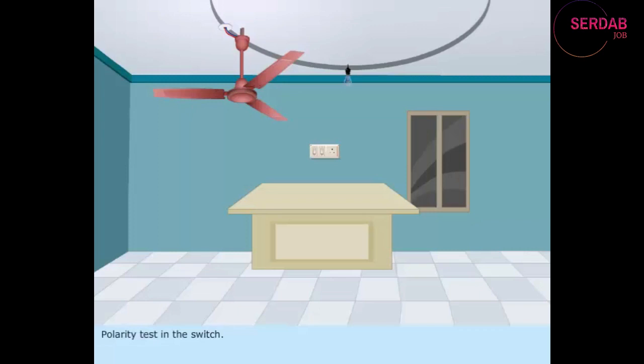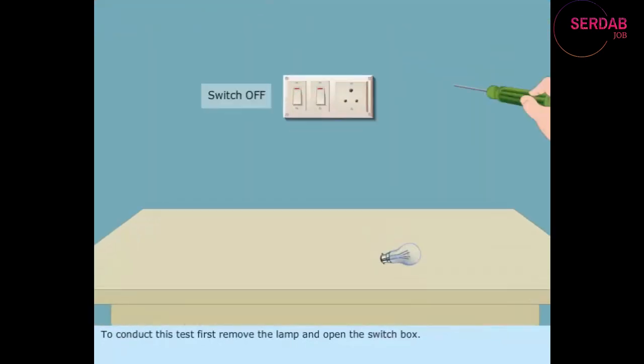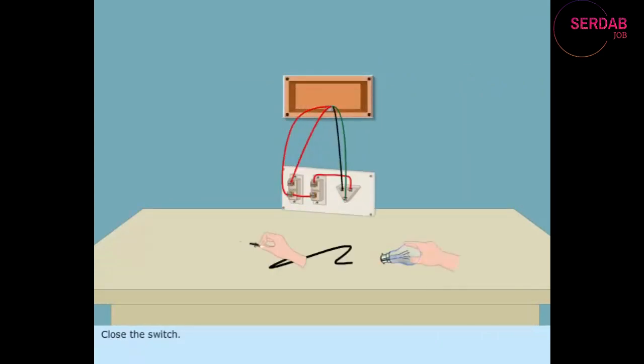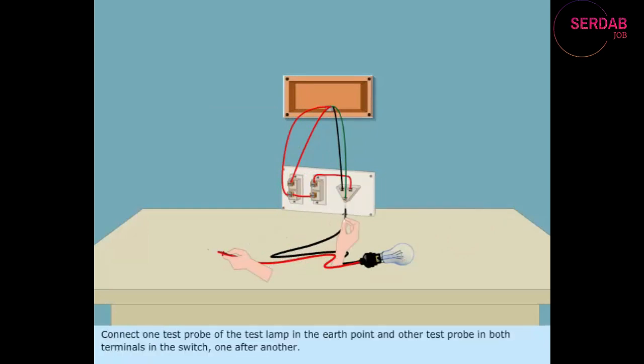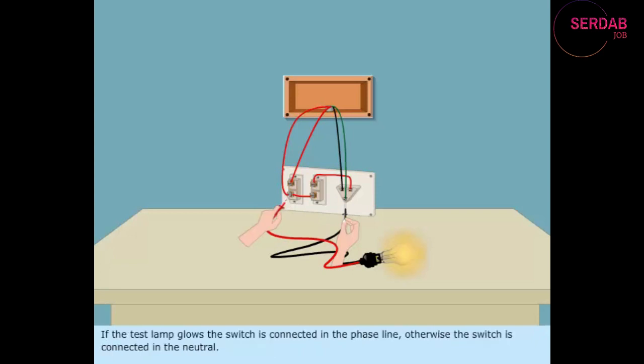Polarity test in the switch. This test is conducted to check whether the switch is connected in phase wire or not. To conduct this test, first remove the lamp and open the switch box. Close the switch. Take a test lamp. Connect one test probe of the test lamp in the earth point and other test probe in both terminals in the switch, one after another. If the test lamp glows, the switch is connected in the phase line, otherwise the switch is connected in the neutral. If the switch is connected in the neutral, correct the connection.